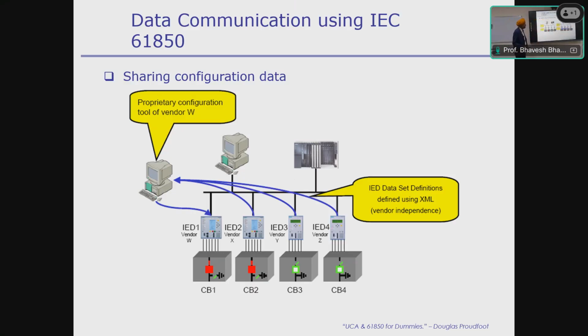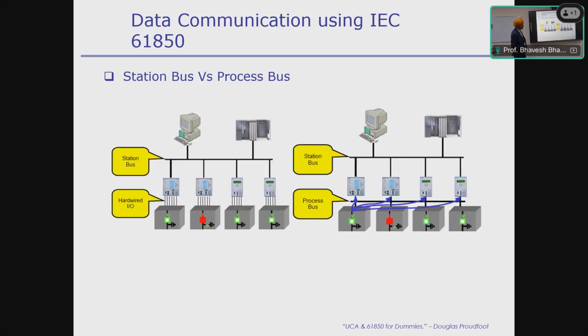So you can share that information, and this is what I was saying. Most substations now have IEDs hardwired from the breakers or from the CT/PTs. At the station bus, we have IEC 61850, but this is where we want to go also. The process bus also should be IEC 61850 compliant, and it should be networked, so then you can share all this information from anywhere with everything.